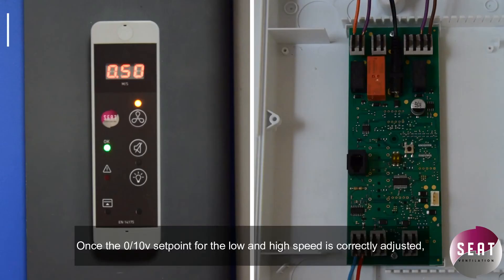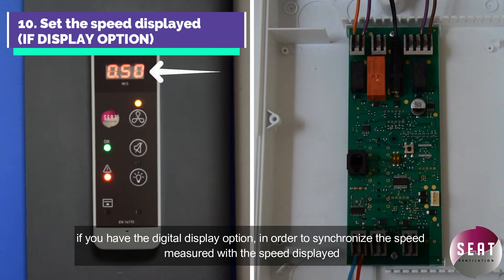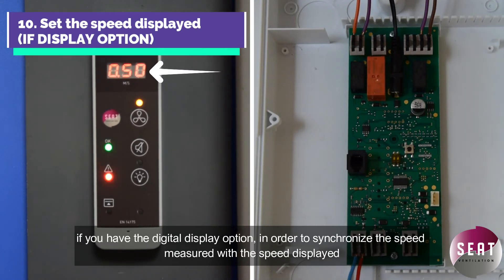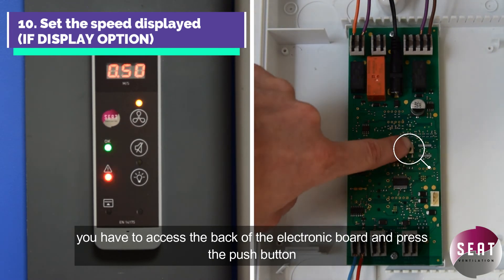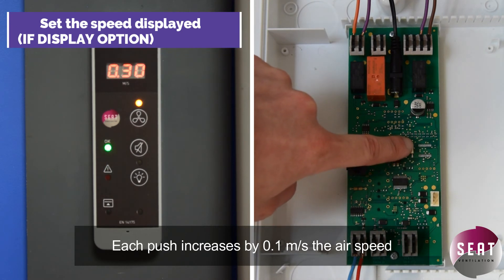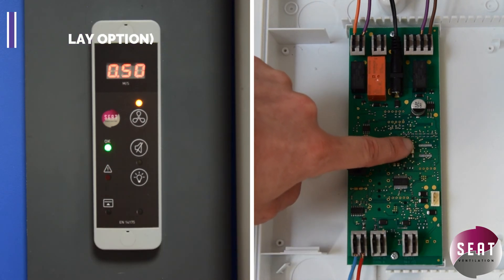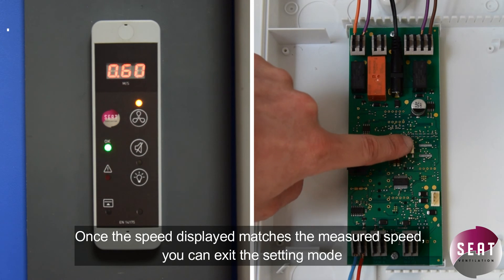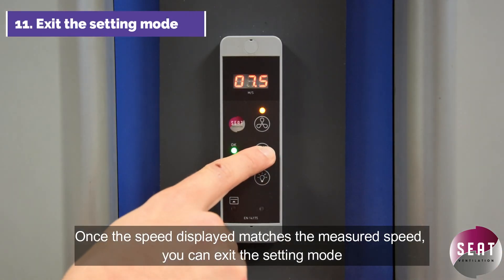Once the 0/10V setpoint for the low and high speed is correctly adjusted, if you have the digital display option, in order to synchronize the speed measured with the speed displayed, you have to access the back of the electronic board and press the push button. Each push button press increases by 0.1 meters per second the airspeed. Once the speed displayed matches the measured speed, you can now exit the setting mode.